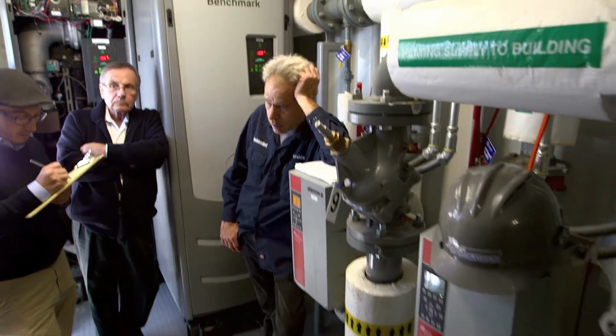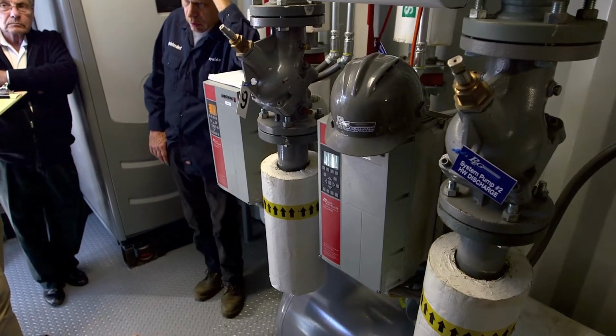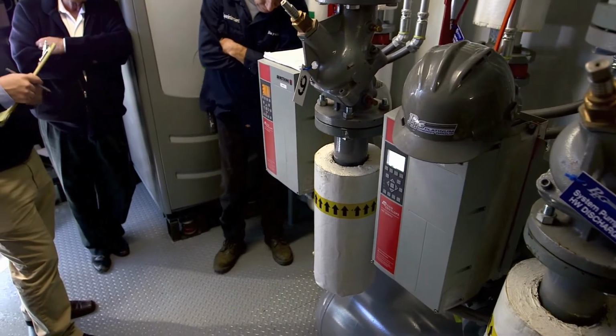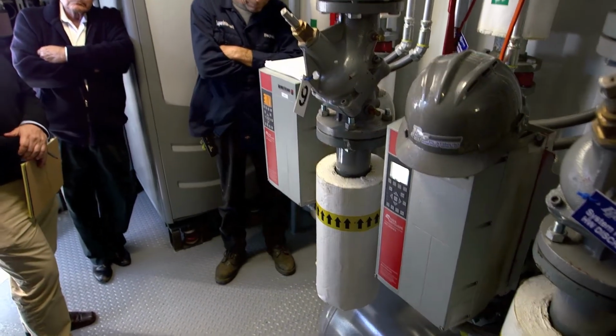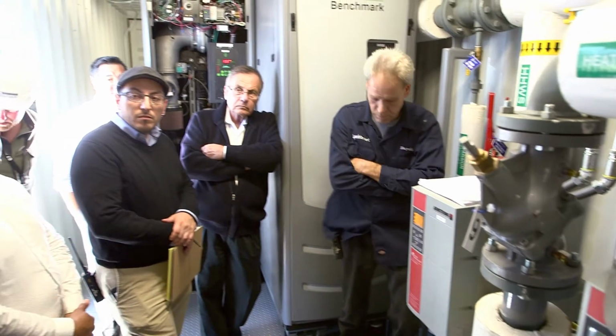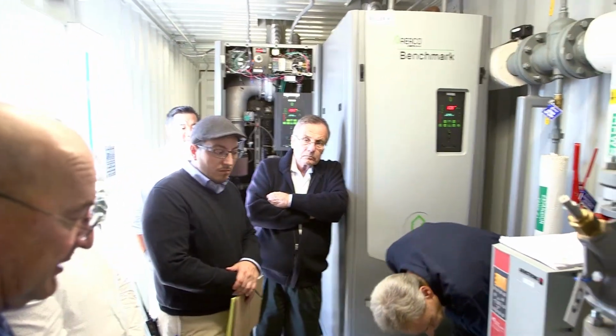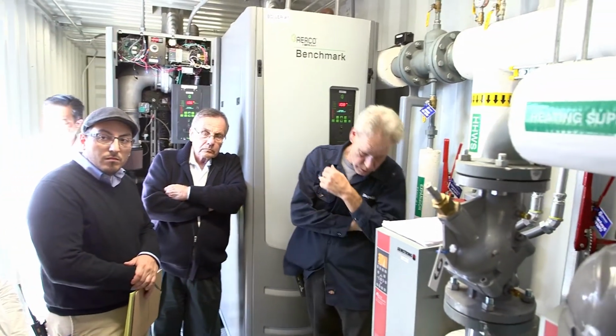Again, the expansion tank has a relief valve. That's telling you, the boilers, I'd be surprised if that's relieving and the boiler relief valves aren't relieving, but it could be just a bad relief valve on the tank. They're required by code now.